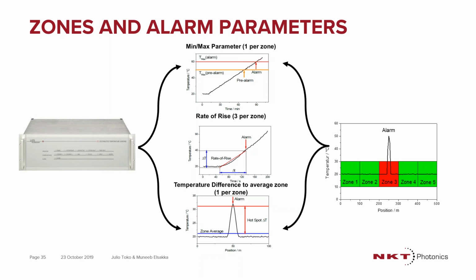So you can do 5 alarms and pre-alarms depending on what fiber optic linear detection system you're using, but this is what makes the system interesting. You don't have to decide from the beginning of your project, do I want a 65 degree Fahrenheit linear detection wire? Do I want a 150 degree Fahrenheit? You don't have to make that decision. Do I need a rate of rise system? Especially for performance-based applications, you can make that decision after. So you set your alarm parameters much later, based on the installation.